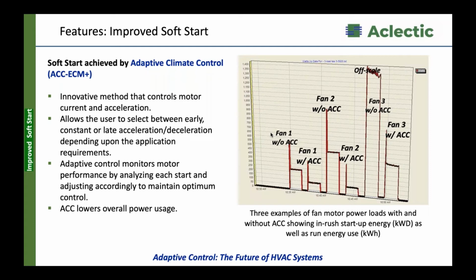But anyway, the point is that we take that same dead short and add smarts to it and say, don't go and send full power rushing in when the motor is not spinning yet. Let it get up to some motion, and we delay it enough such that we're creating magnetic field, creating resistance, diminishing the inrush current and giving that motor some smarts again. So the one box you see on 3 different fan sizes, the one on the far right there, the spike is so high you couldn't even fit it on the same page. But you get the idea, we reduce kWd as well as kW and kWh. Next slide.